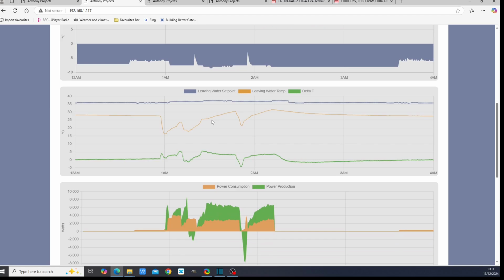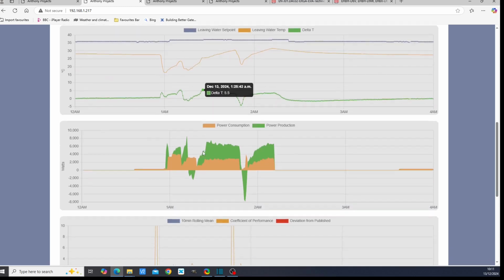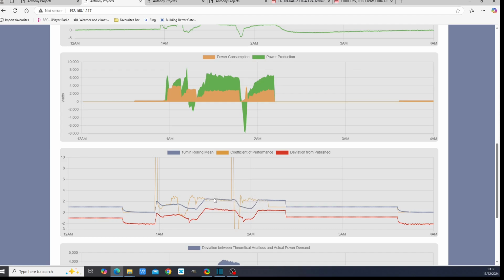But we'll have a look at the coefficient of performance in this operating regime here. I've added 2 new lines. This one here is the flow return temperature difference, and then we've also got this one. So this blue line is the coefficient of performance 10-minute average, and this one is the deviation from the published figures. And there aren't too many published figures. There's about 5 figures for different temperature ranges, and there's one at -10, one at -2, one at 2 degrees, one at 7 degrees, and those are the only regimes I've got for measuring for published figures. But as you can see, we're doing better than the published figures here.